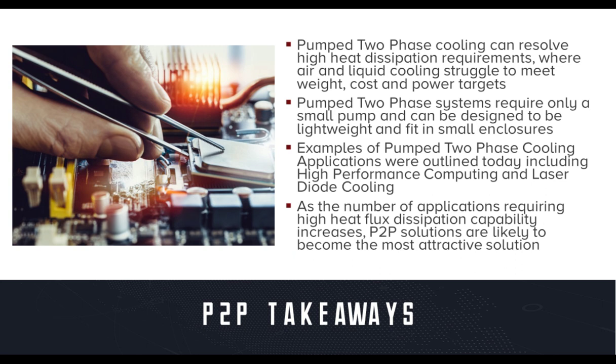To summarize, pump two-phase cooling offers the potential to address increasing heat dissipation requirements up to 1,000 watts per centimeter squared by some estimates, in which air and pumped liquid cooling just cannot compete. Pump two-phase systems require only a small pump and can be designed to be compact and lightweight. We have reviewed some applications where pump two-phase systems are being implemented today, including laser diode applications, high-performance computing applications, and power electronics applications. As the number of applications requiring high heat flux dissipation capability increase, we believe pump two-phase solutions are likely to become the most attractive solution.